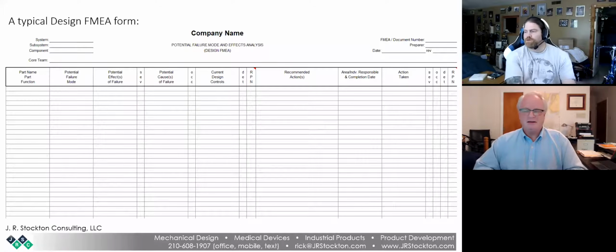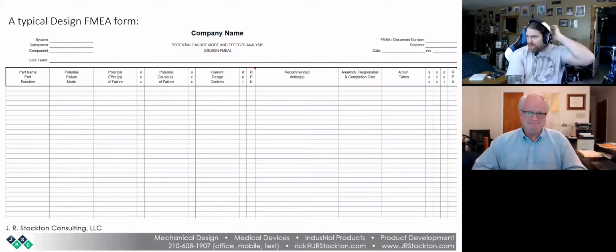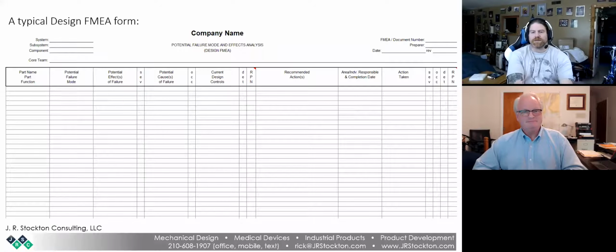No, I think you covered it really well. I've seen a lot of companies, they'll say, well, this is the highest RPN score we can have for acceptable risk. And as the auditor, you're trained to say, well, how did you come up with that number?